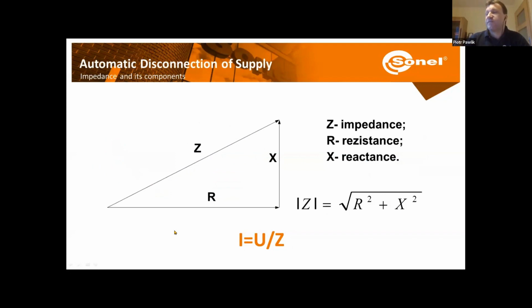But in case of AC systems, we need to measure fault loop impedance because we are expecting that in our systems there will be some resistance coming from, for example, wires in the walls. But our transformer also has some coils, so it will have some reactance part. And that's why we measure the impedance, which is the summary of resistance and reactance. And further on in our network, we need to know the fault current flowing in case of a fault situation, and that is going to be our supply voltage divided by the measured fault loop impedance. And this is the fault current or prospective short circuit current.